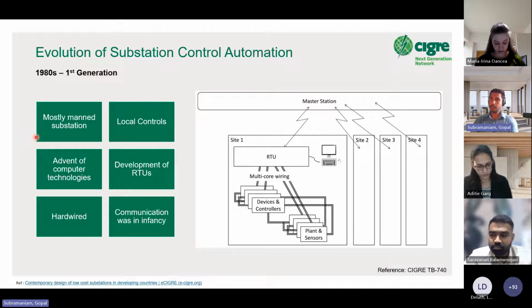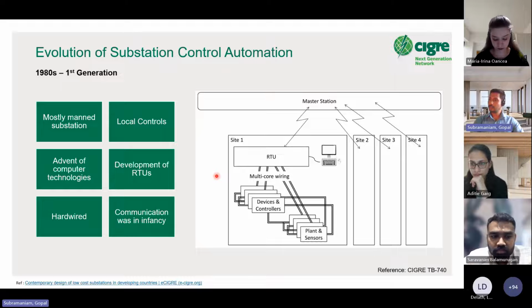Around the 1980s, most substations were manned, and communication existed only between the RTU and the control center. Communication between plant equipment or relays was almost nil, as these were the days of electromechanical relays or single function static relays. Most of the controls were hardwired and local.